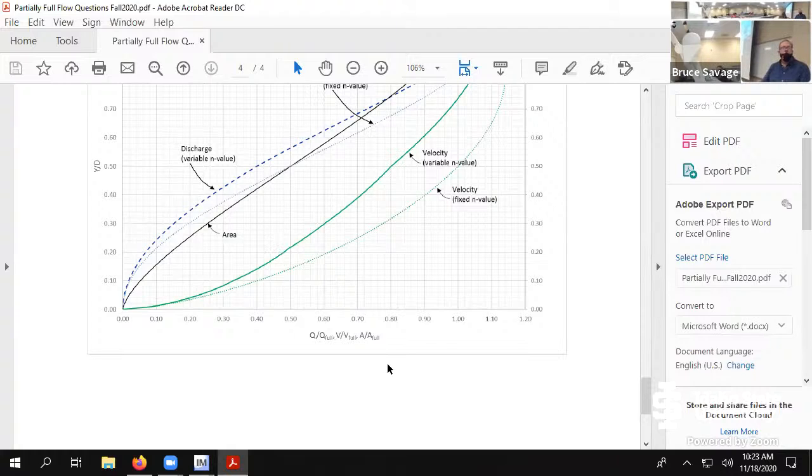Because you could stick a pump inside your network, a booster pump. I mean, this is a real world thing. The pump is not always just located on the pseudo loop. It could be located on a regular loop. And so it depends on the direction of your loop, whether it's pseudo or a regular loop, on whether it's positive or negative. Okay. And it's like following the hydraulic grade line around.